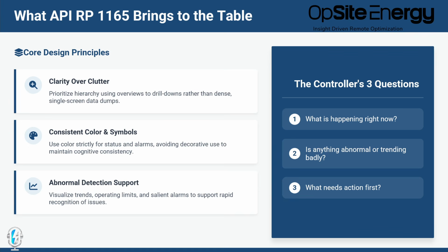Because if I'm getting it in a blinking fashion with an alarm, the controller has to quickly know, okay, I've got to take this alarm first. It's not just my first out, this one's a priority. It's established as a priority 1 or whatever your priority levels are, which is what you spell out in 1165. So I got that right. If you're really looking at design, those are the 3 main elements. You better be asking yourself these questions as you move through the design.